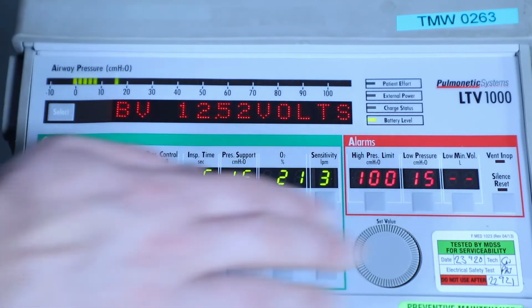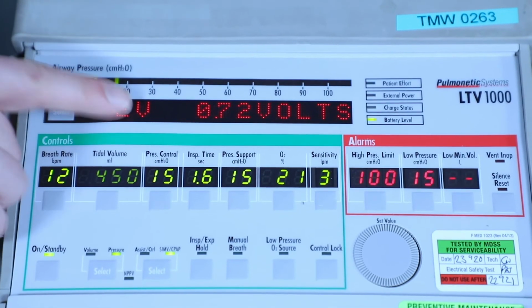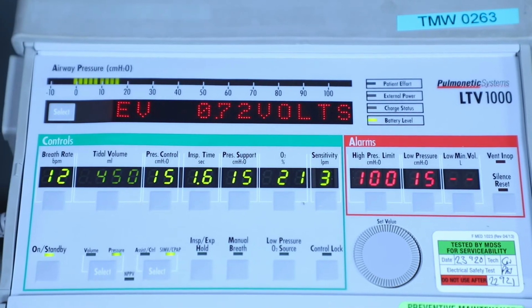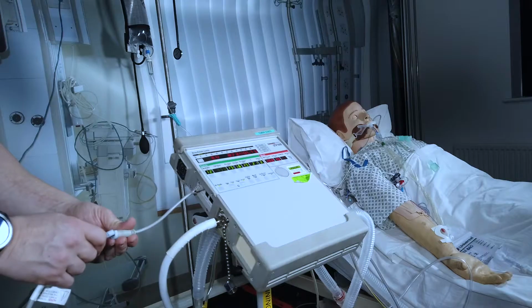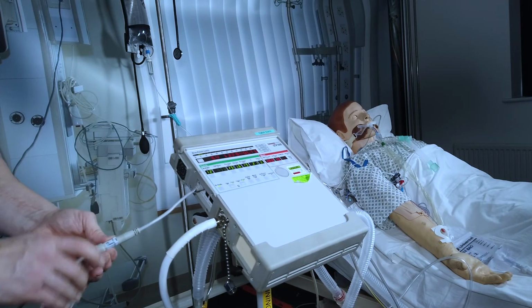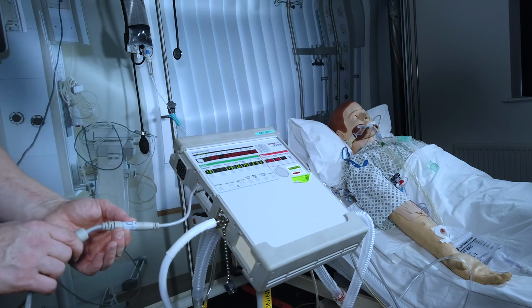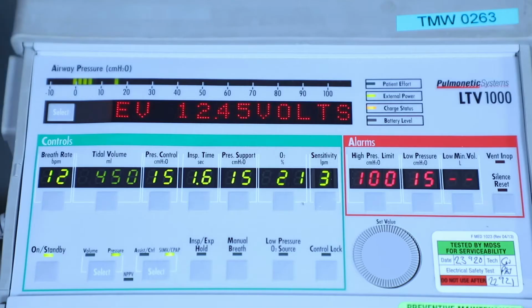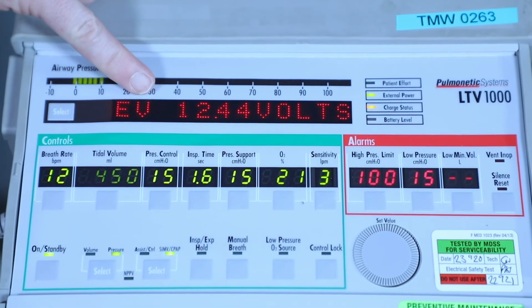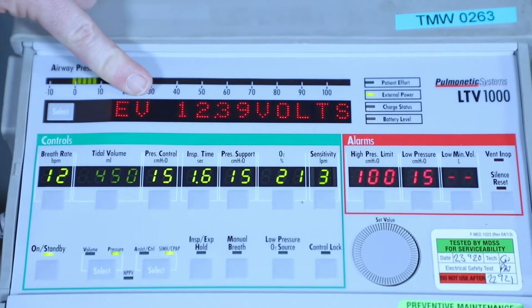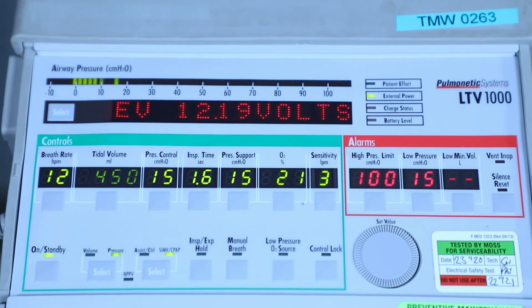We now want to test an external power source, so we'll test our 12 amp hour battery. So if we select the external voltage and then connect up the 12 amp hour battery. Connect the external battery up in a similar way to connecting up the mains adapter. And again, we want to confirm that the voltage for this battery is above 12, as long as the battery has been fully charged. Once we've done this, that's the checks complete.